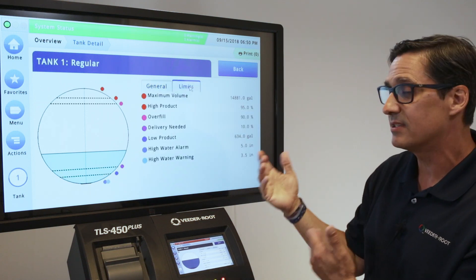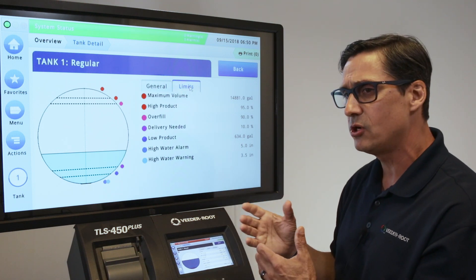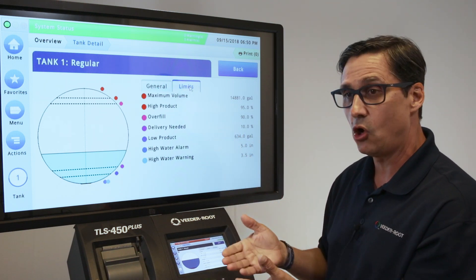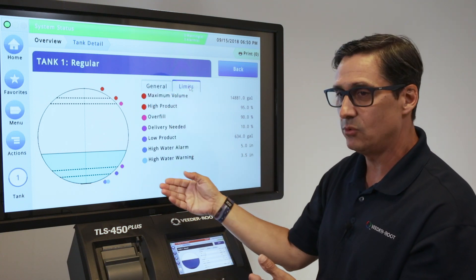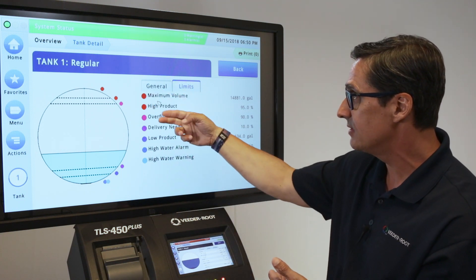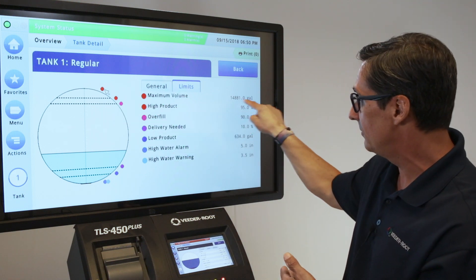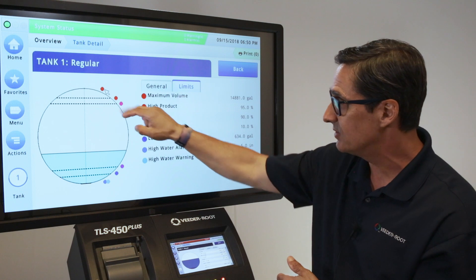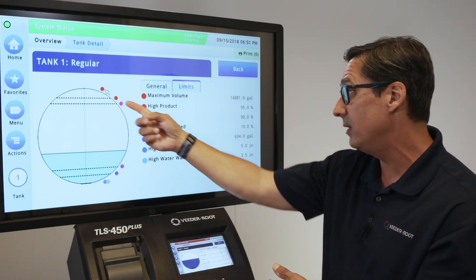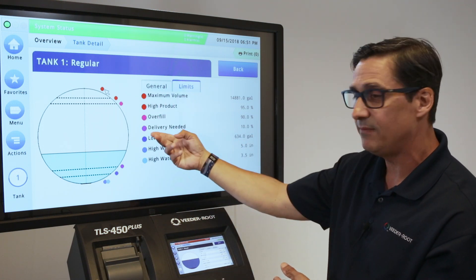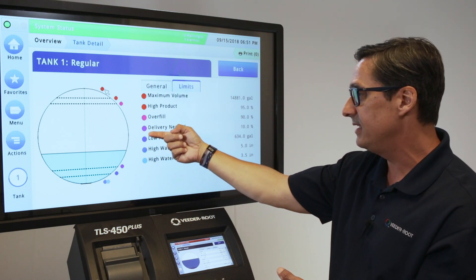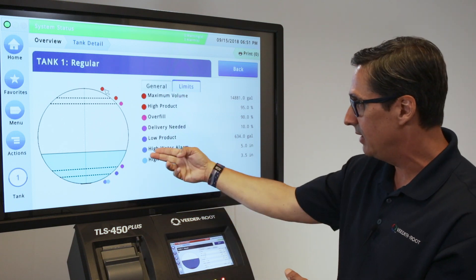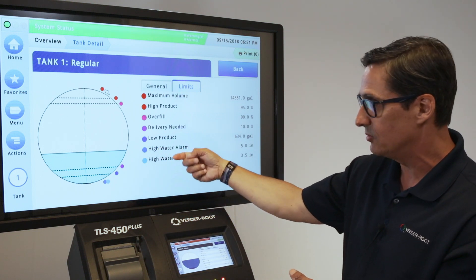The Limits menu is a nice menu to have. If you're not sure where your system is programmed to set for alarms, this gives you a nice visual illustration of where those alarms are set. For instance, a maximum volume alarm is the maximum capacity of the tank. High product is set at 95 percent. The overfill, which is a regulatory requirement, is set at 90 percent. If you want the TLS system to generate a delivery needed alert, you'd set it at 10 percent. And then water height for alarms and warnings.